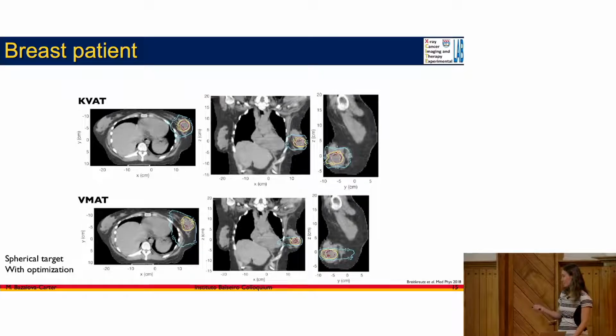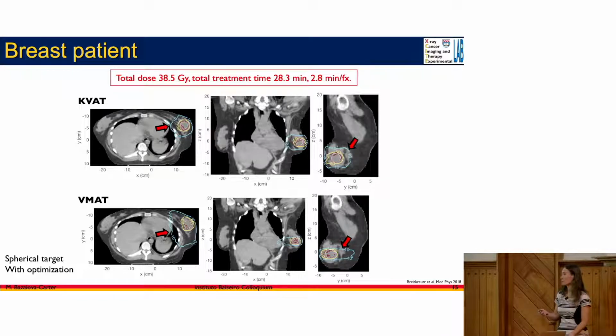And you'll see a number of things again. So these are all the views and the dose distribution superimposed on CT images. And if you look closely, you can see that actually the 10% isodose lines, again, we want this to be as tight to the tumor as possible, because that means that we are not irradiating healthy tissues, is actually tighter around the tumor in our kilovoltage arc dose distributions. And it's shown over here, and it's shown in the other view as well. So we were very pleased with these results. And this is done with treatment planning optimization, but still on a spherical target. Unfortunately, targets are not very spherical. We also had to look at the treatment time.